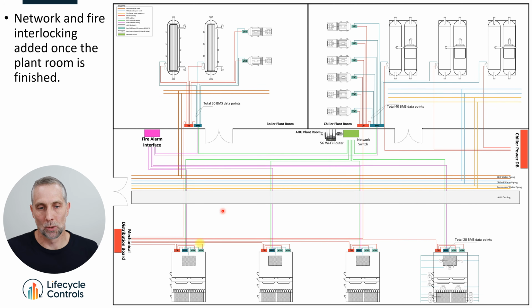So, and over here now, we installed the stuff on the AHUs months before. We temporarily powered the AHU because we now made it easier to temporarily power one part at a time, one part at a time, one part at a time. And now later on, as the mechanical progressed with their pipe work and duct work, and the mechanical electrician perhaps progressed, now you've got to get a network around the controller. So you quickly run a network cable to each controller. Of course, it's still across the whole plant room, but that's a much less work. And also, you've already commissioned much of the inputs and outputs. You just get the network installed now.